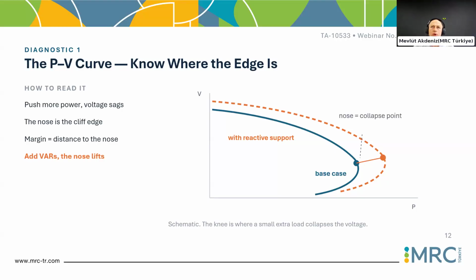But there are some incremental analysis approaches, which are practical and analytically proven, used in TSOs. PV and QV curves are among these, like short circuit assessments. We just do some incremental load flow analysis in some weak buses or sample buses, or even in all main buses. Once you have implemented load flow with incremental active power, we can plot the voltage variation in the grid depending on the incremental active power load, which gives critical and valuable insight on this bus bar. It means that if you absorb additional incremental power from the bus bar, you approach the edge point, and this edge point is theoretically the unstable part of the grid operational points, and it really depends on N-1 also. So the number of lines connected to a substation is also critical.